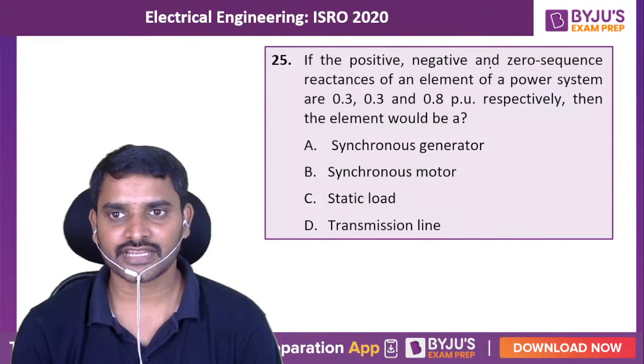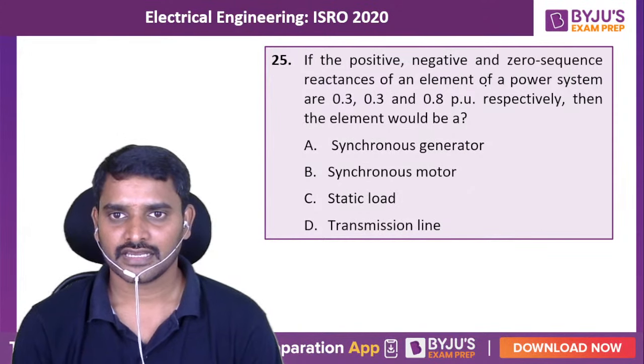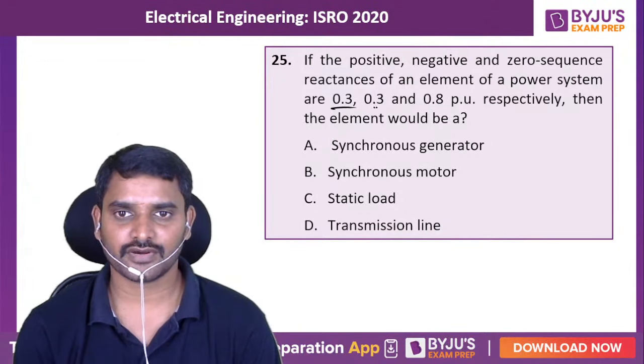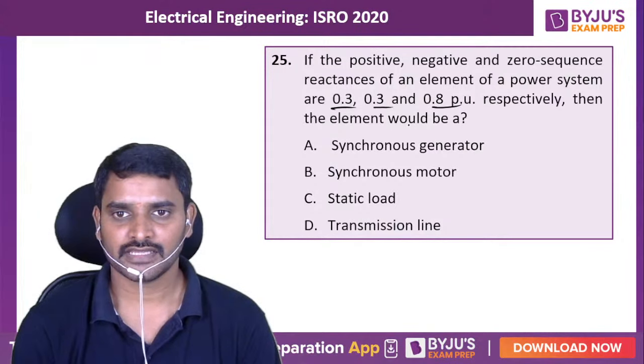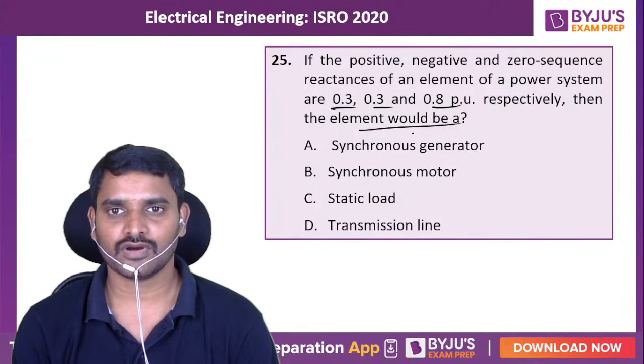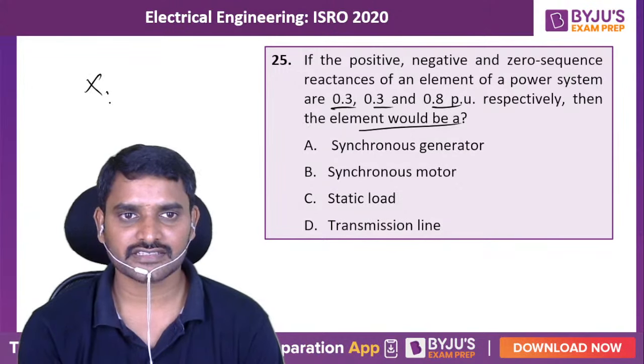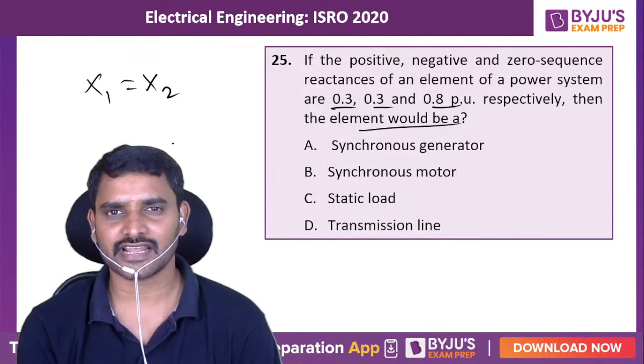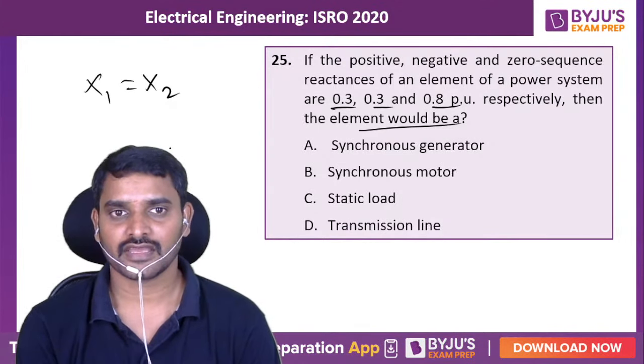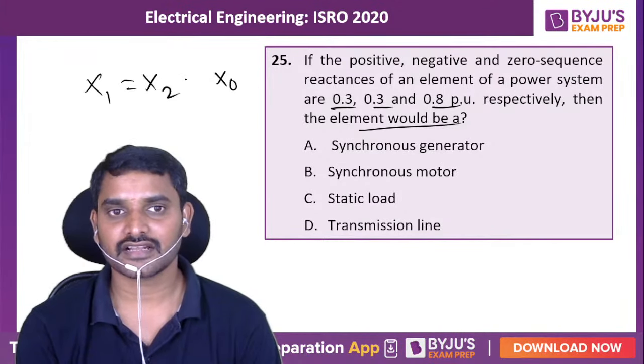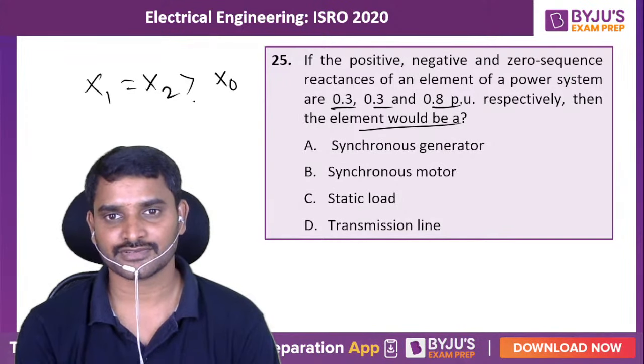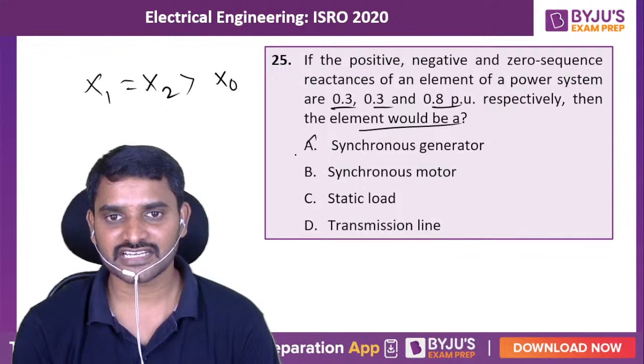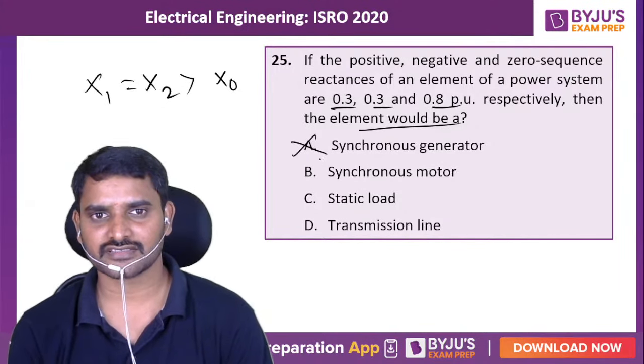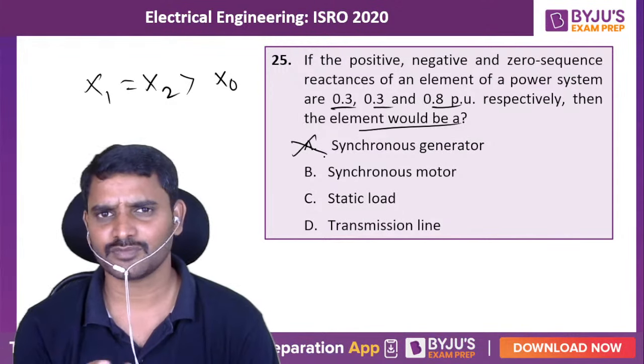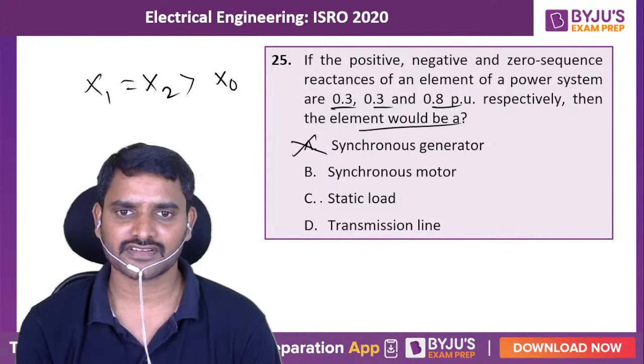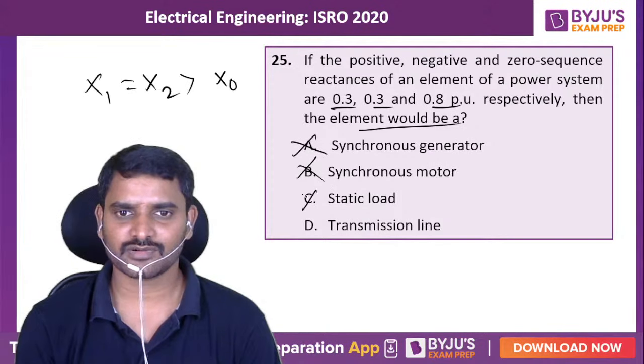If the positive, negative and zero sequence reactances of an element of a power system are 0.3, 0.3 and 0.8 per unit respectively, then what is the element? Positive sequence reactance and negative sequence reactance are the same. Generally for a transformer also it will be the same. But zero sequence reactance is greater than positive and negative sequence reactance. For a synchronous generator, positive and negative sequence reactance sometimes will be different, sometimes the same. For a synchronous motor also. For a static load, it is not like that.